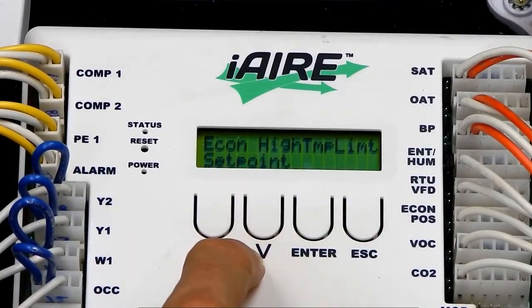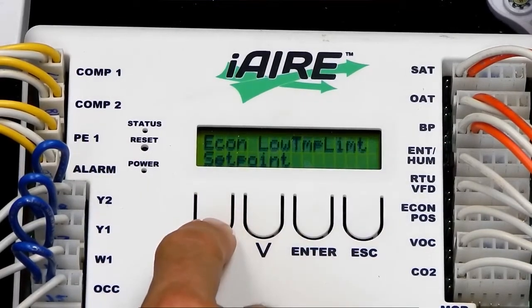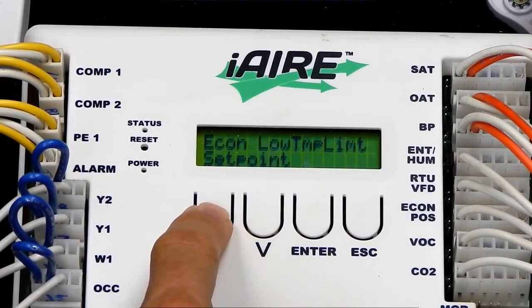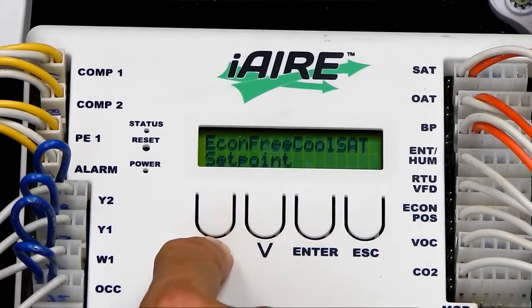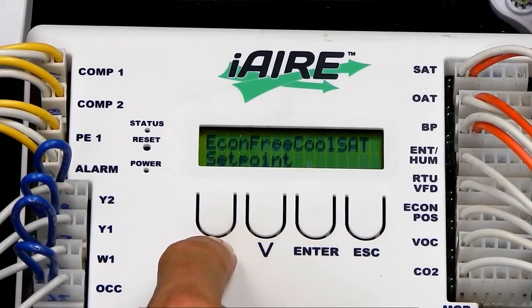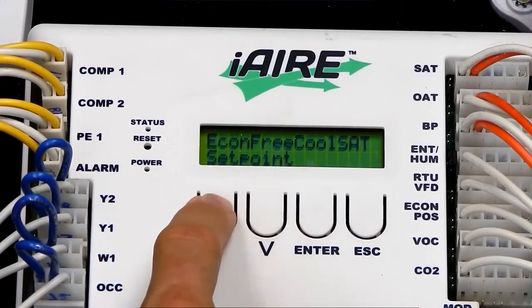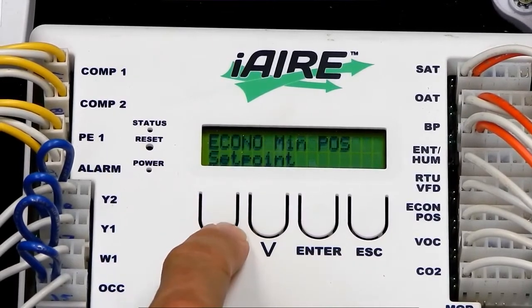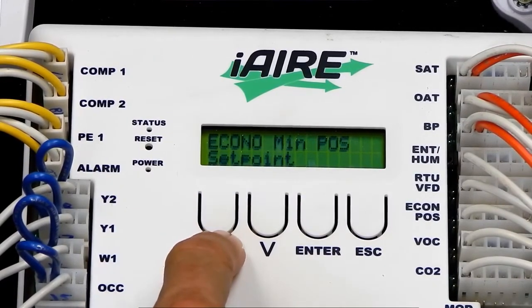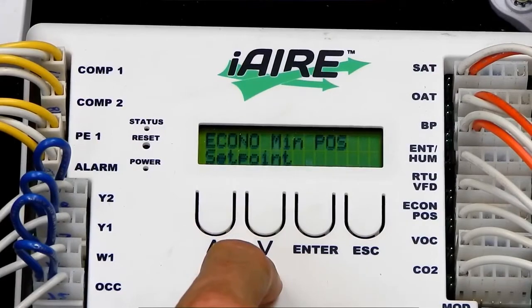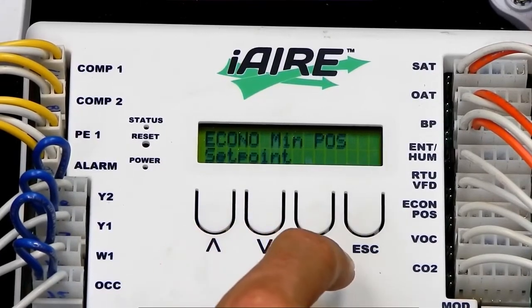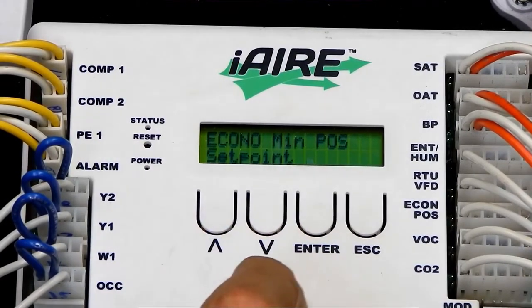You'd set the high temperature limit, the low temperature limit to prevent coil freezing, the free cooling supply air temperature set point for where your damper is going to be controlled to on the discharge of the RTU, and the economizer minimum damper position that would bring in your minimum outside air except for free cooling. Once you're through that, the setup is complete.